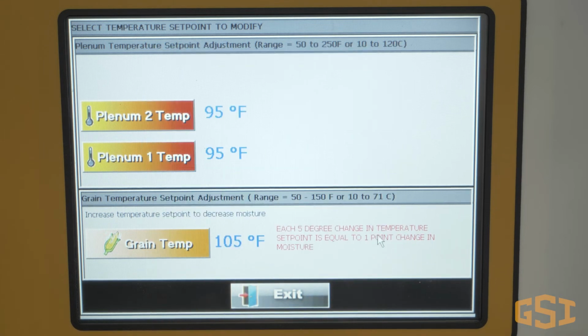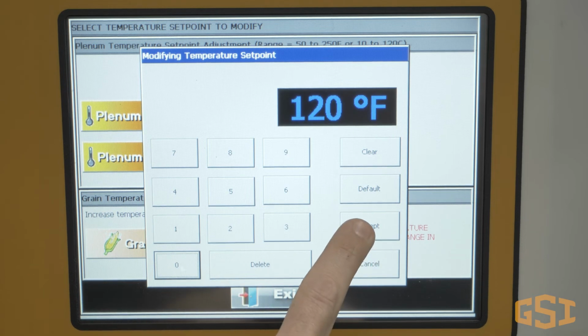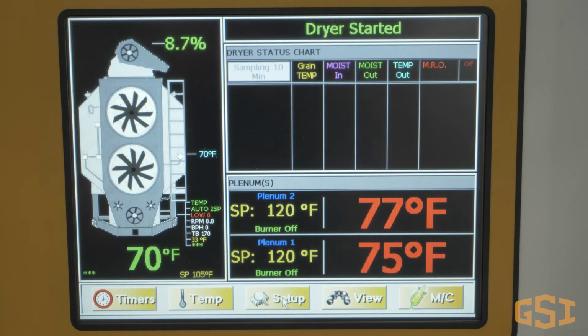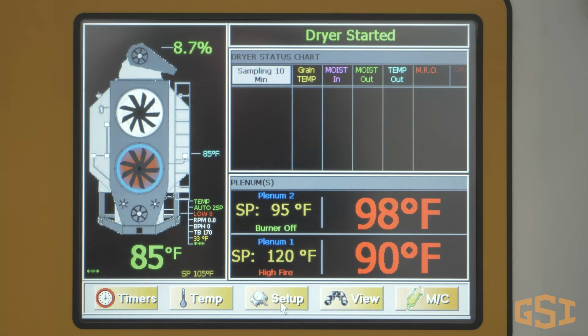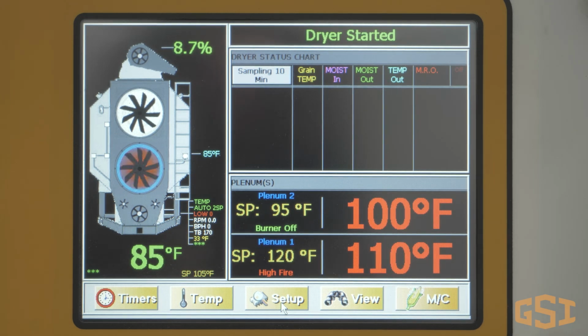The vision control system constantly monitors plenum temperature inside the dryer and the amount of fuel going into the burner to reach and then maintain a constant temperature that is set by the operator. For our example, let's adjust the plenum set point to 120 degrees Fahrenheit. Your set point will likely be very different. When the burner first comes on, the maximum amount of fuel based on your regulator setting enters the burner and the plenum temperature increases towards your set point. This is the best time to watch the light in the burner switch to see if the flame probe is in constant contact with the flame when the burner is on high fire.